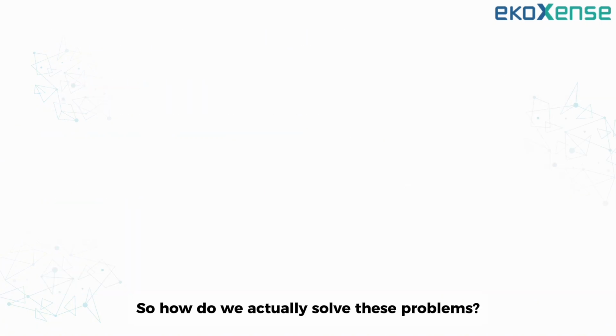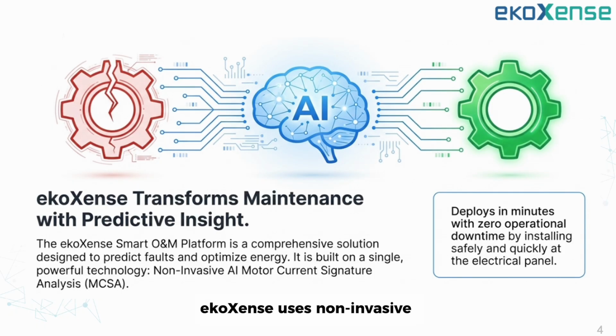So how do we actually solve these problems? ekoXense uses non-invasive AI motor current signature analysis, or MCSA, to transform maintenance. For system integrators, the biggest advantage here is speed. Unlike vibration sensors that require machine shutdowns and complicated installation, our solution can be deployed in minutes with zero operational downtime. Everything is installed safely at the electrical panel, so you can scale quickly across a factory floor without interrupting production for your client.